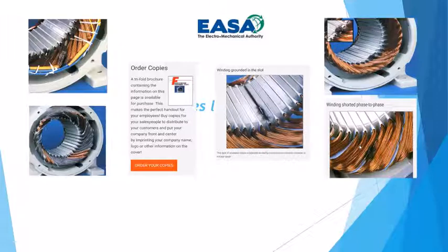Over here on the far right, you can see this was again voltage to ground, was caused high for some reason, and it popped and pierced the insulation on there. And then the final one shown here is phase to phase. Between these two pieces of slot insulation, there's a set of coils here, and between phase A and, let's say this is phase B, that voltage potential is 480 here. If that voltage between phase A and phase B got too high, it ended up wanting to jump and arc across and blew the winding out. So it gives you resultant information.